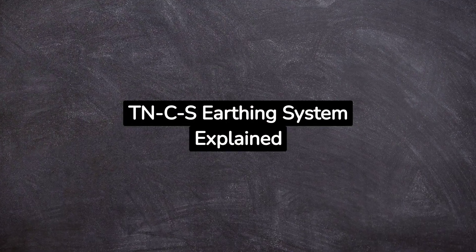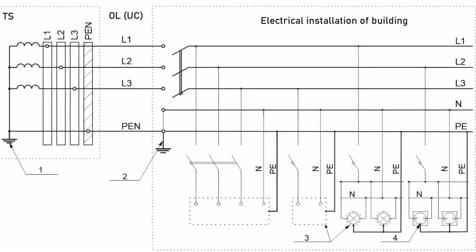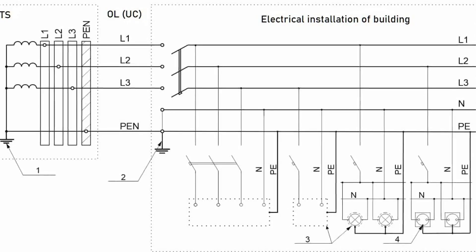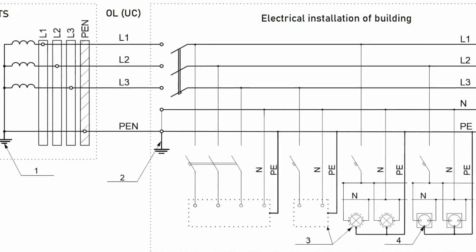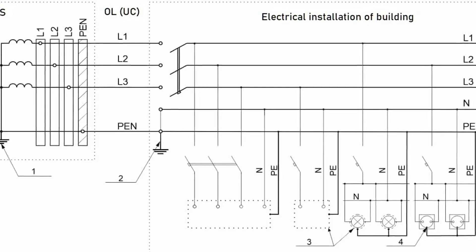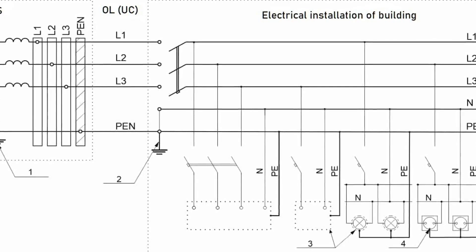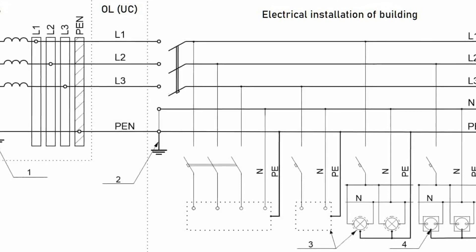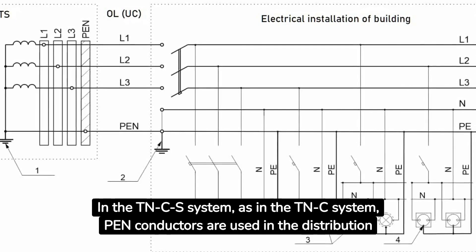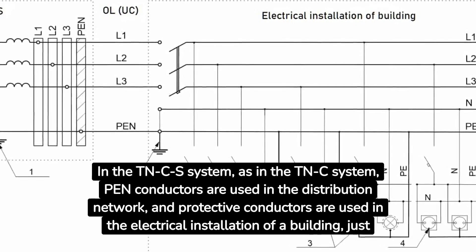TN-C-S earthing system explained. In the TN-C-S type of system earthing, one part of the power supply that is live is earthed — usually the transformer neutral. The exposed conductive parts of the electrical installation of a building have an electrical connection to the earthed live part of the power supply. PEN conductors are generally used in the LV electrical distribution network, while PE protective conductors are used in the electrical installation of a building — as in the TN-C system for the network and the TN-S system for the installation.